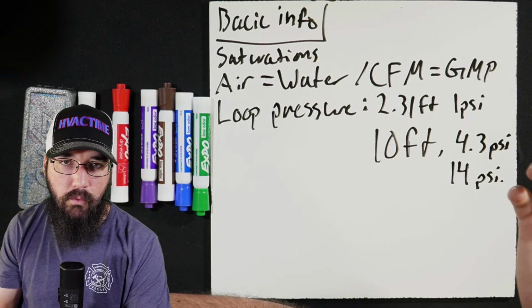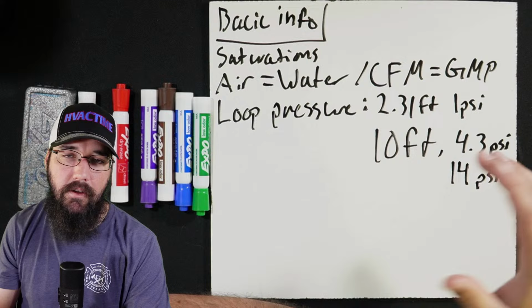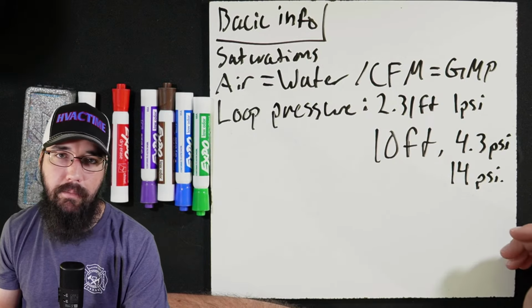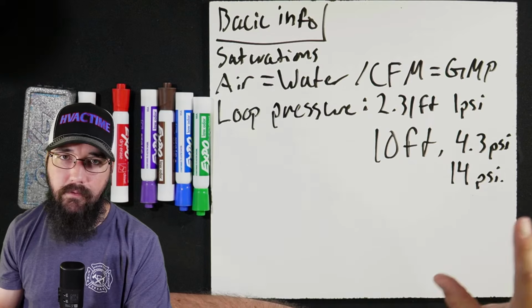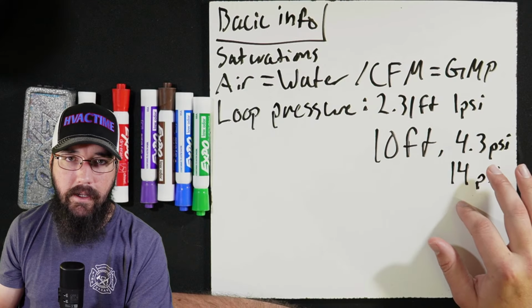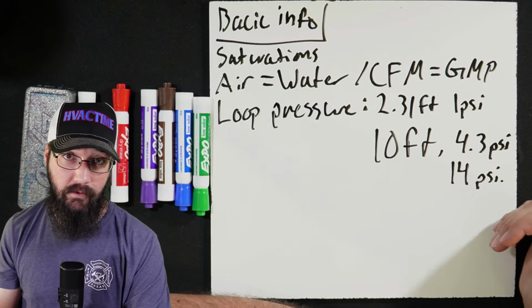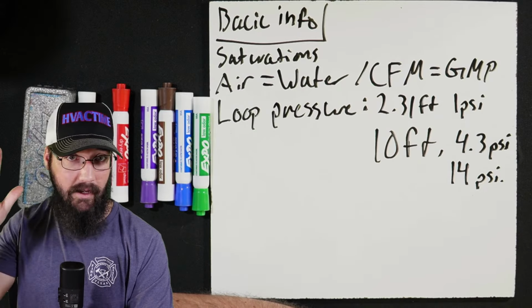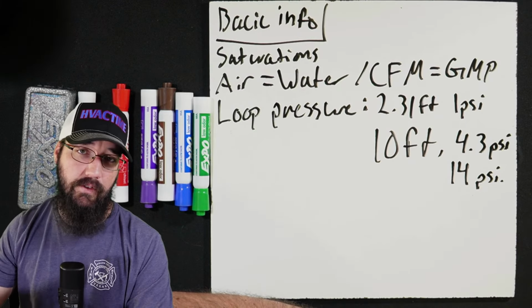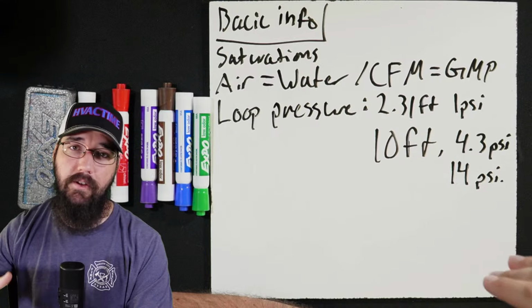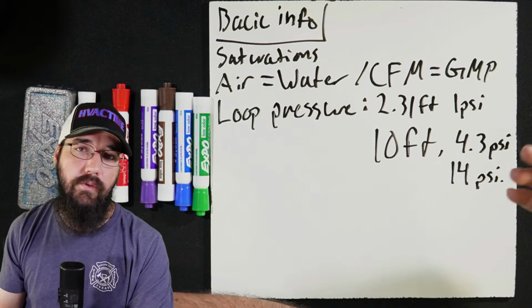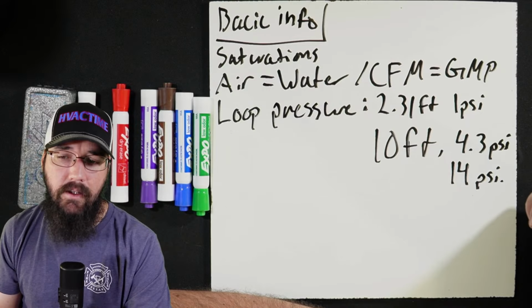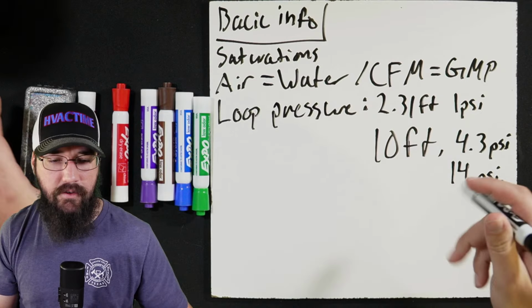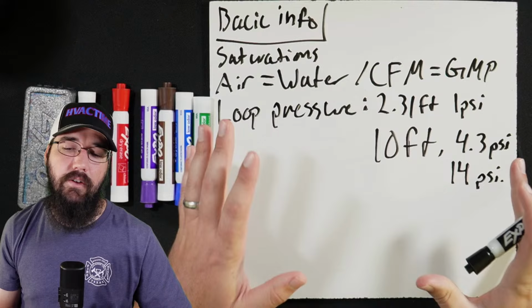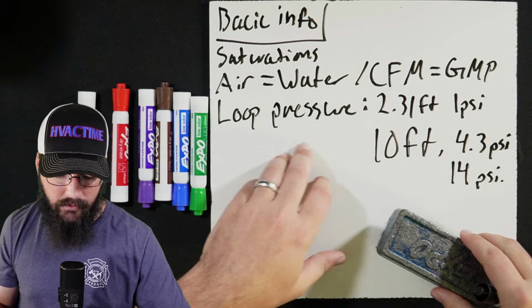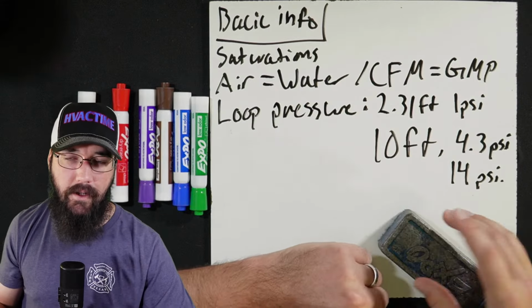Well, what pressure should you start with? And it's not a default answer, right? It's not, okay, well, I should have at least 20 psi, 30 psi. There's no rules of thumb here, okay? It's calculated based off of that specific loop and its design, its height. You could have one facility that's 10 feet, one facility that's 20 feet per floor. Those are things you have to think about. My point being there, understanding your loop pressures is also going to help you get started.